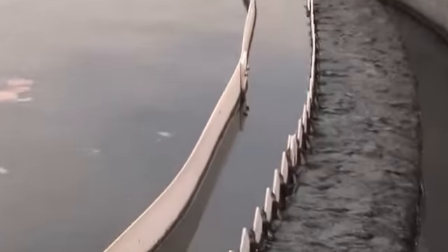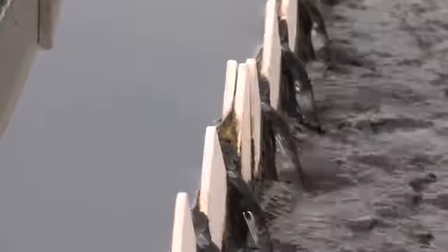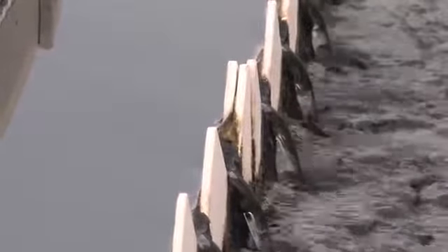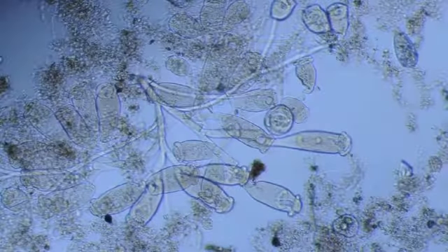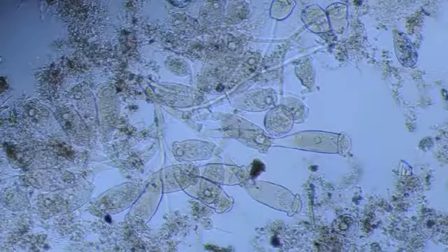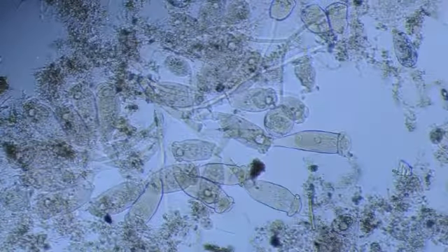By identifying the organisms and by quantifying and tracking their presence, one can use that information to understand and identify the potential effluent quality you would see. For example, Vorticella and Epistylis are seen normally with high quality effluents, whereas Opercularia is seen more often in a lower quality effluent. This English study was updated to reflect the condition for nitrification in a wastewater treatment plant.